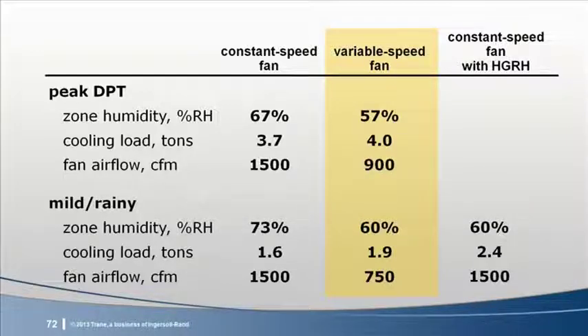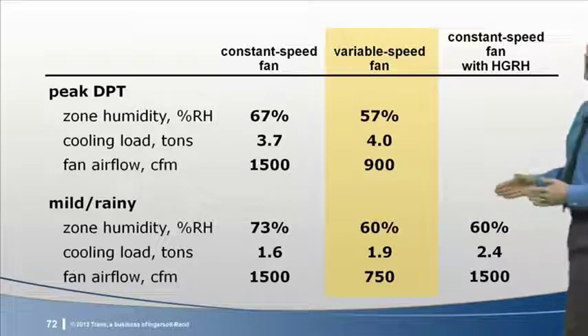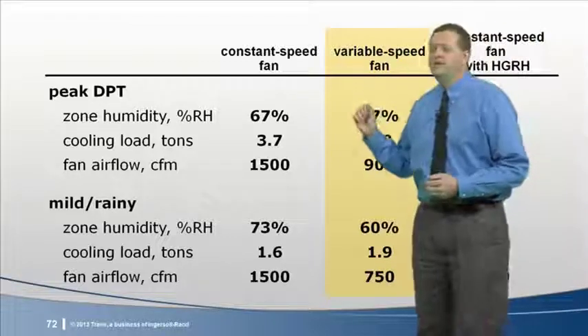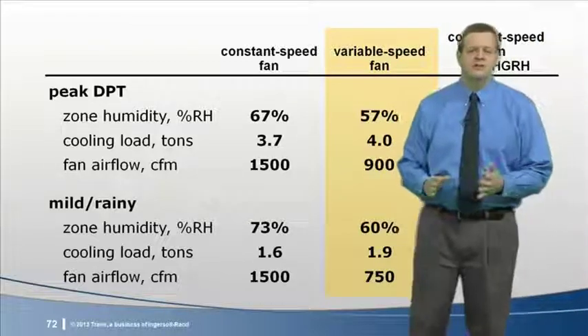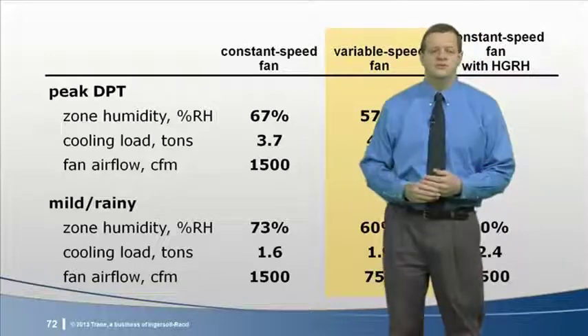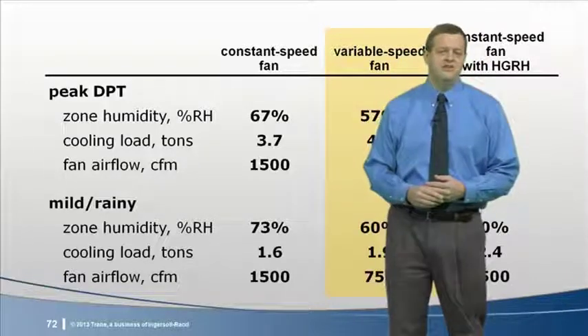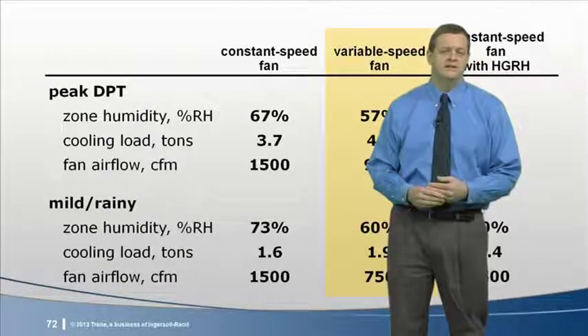In order to limit space humidity to 60%, a constant volume system will overcool the air to dehumidify it and then reheat it to prevent overcooling the zone. This requires more compressor energy along with more fan energy. For many applications, the variable speed fan may do a good enough job of limiting indoor humidity levels, so you may not need to equip the system with any other dehumidification enhancements like hot gas reheat.